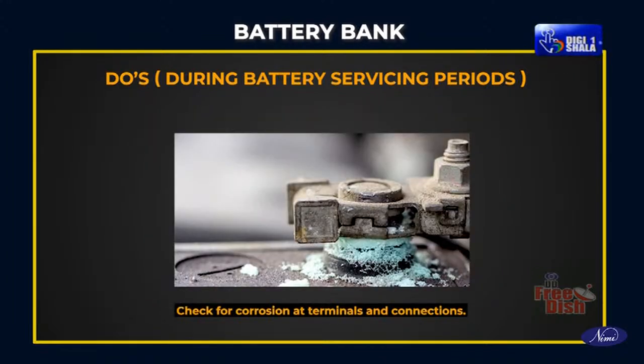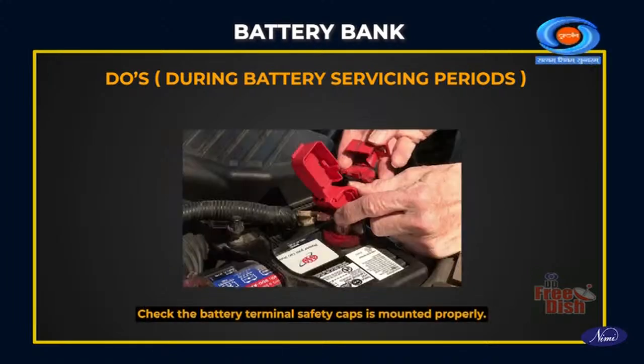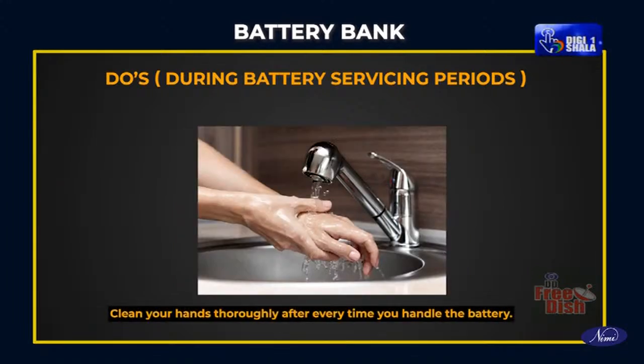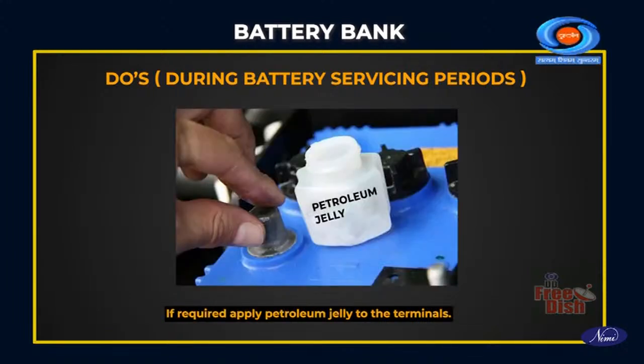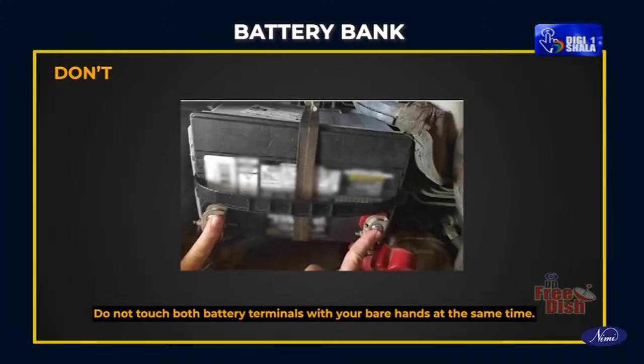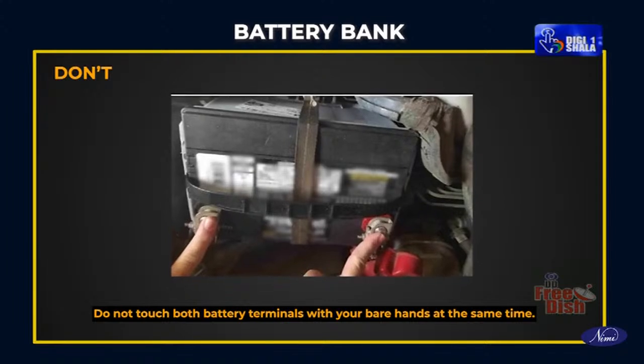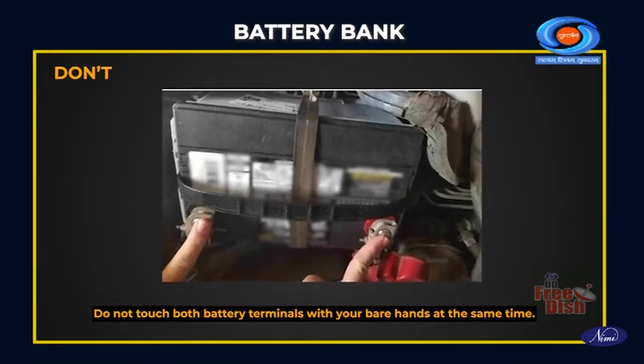Check for corrosion at terminals and connections. Check that the battery terminal safety caps are mounted properly. Clean your hands thoroughly after every time you handle the battery. If required, apply petroleum jelly to the terminals. Do not touch both battery terminals with your bare hands at the same time.